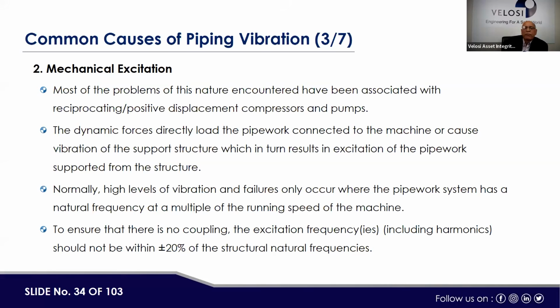Then there are also dynamic forces which are associated with the movement of the pump and compressor, and associated with the pipe work. And then there could be a resonance, like if pump and compressor are vibrating or causing high pulsation, then it may have some resonance on the piping system. If the piping system is not properly supported, anchored, or properly sized, then it may also have resultant high vibration. Now, normally high levels of vibration and failures only occur when the pipe work system has a natural frequency at a multiple of the running speed of the machine. This is a normal definition. To ensure that there is no coupling, the excitation frequencies, including harmonics, should not be within plus or minus 20% of the structural natural frequencies. Here, how to break this relationship? This is through proper anchoring, proper supporting, and proper sizing.